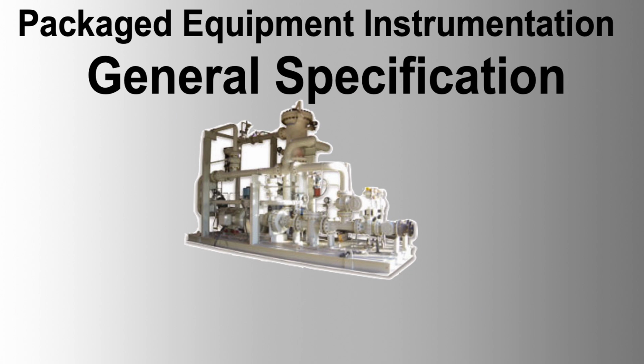Solenoid valves function as pilot devices only, with encapsulated high-temperature coils, 316 stainless steel bodies, rated for 24-volt DC, and seal materials of Buna N or Viton. Relief valves: designed, constructed, tested, and marked according to API 520, 526, and 527, with balanced bellows or pilot-operated safety valves for specific applications. Overpressure limits should comply with ASME VIII standards, and installation should consider direct and unobstructed flow between the vessel header and the valve.